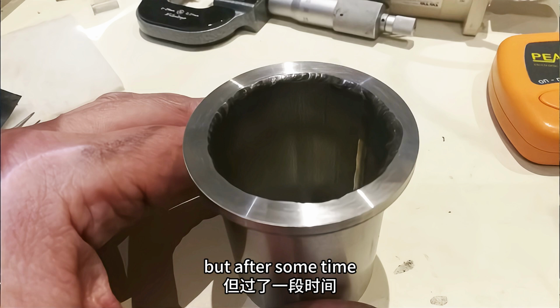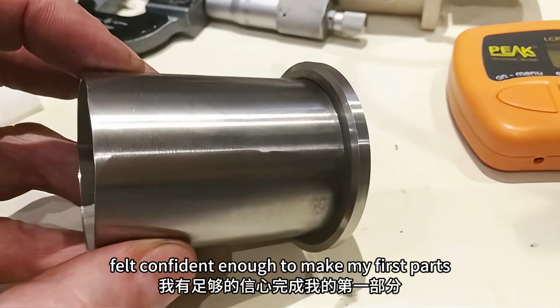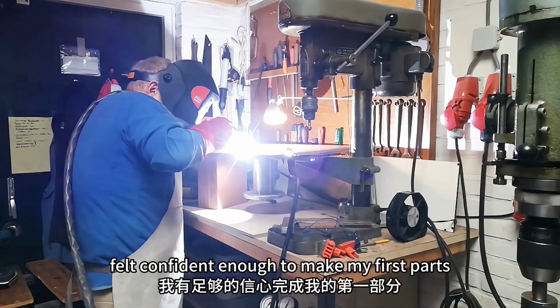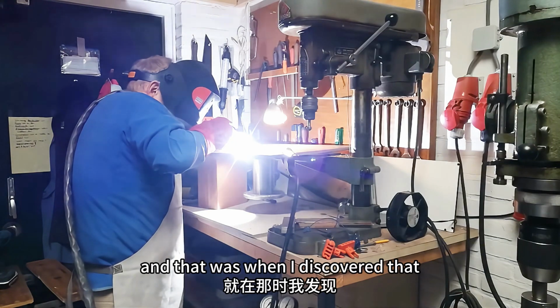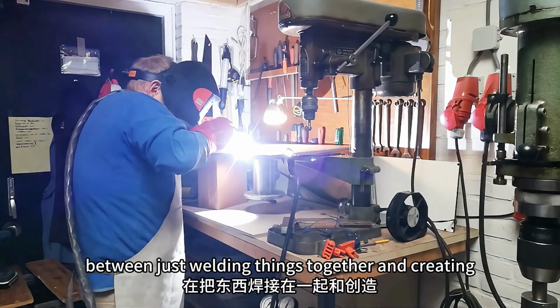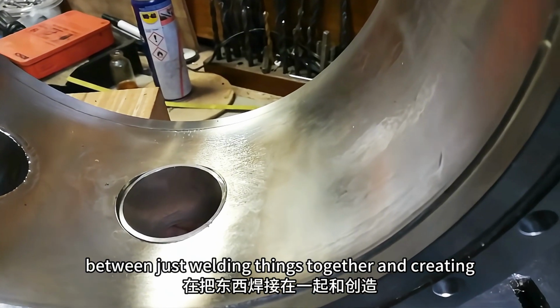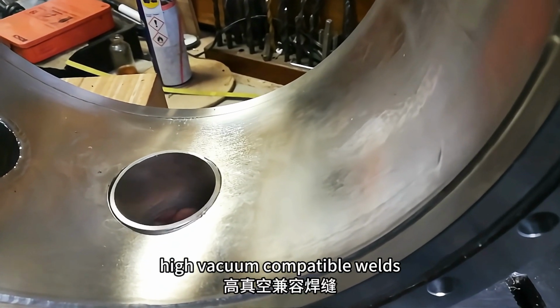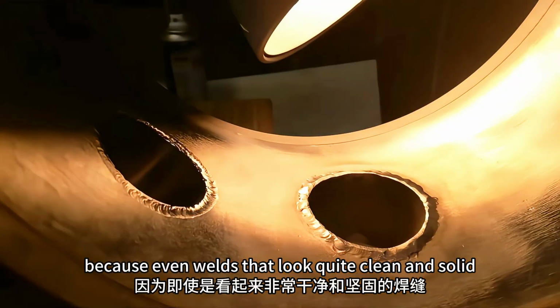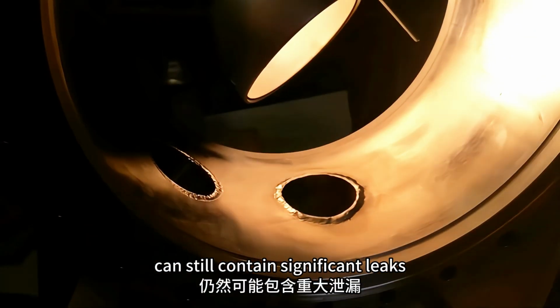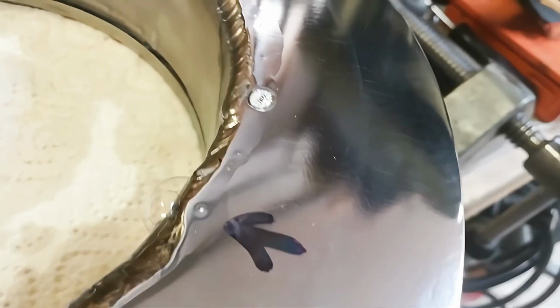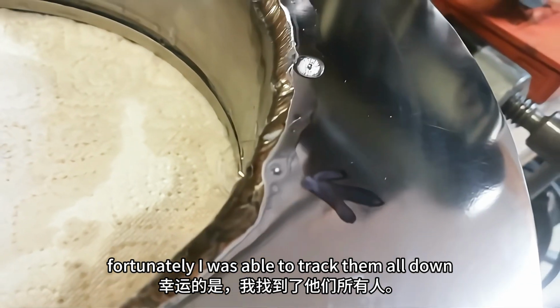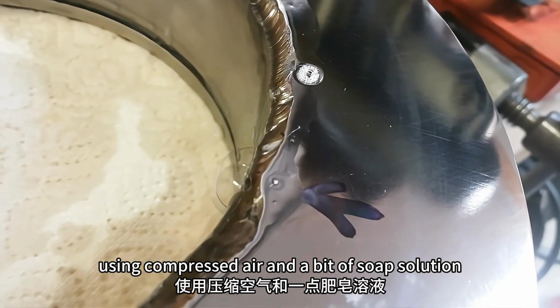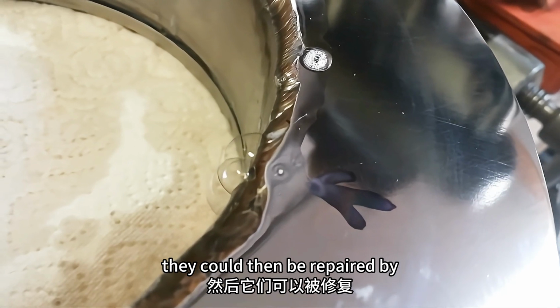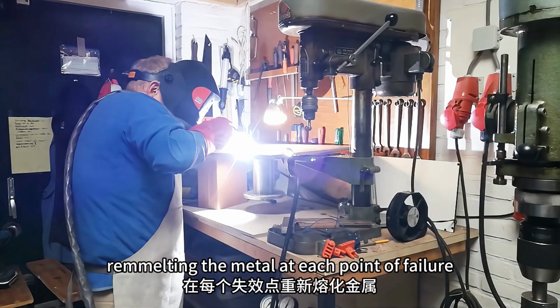But after some time I sort of got the hang of it and then felt confident enough to make my first parts. And that was when I discovered that there is a big difference between just welding things together and creating high vacuum compatible welds. Because even welds that look quite clean and solid can still contain significant leaks. Fortunately, I was able to track them all down using compressed air and a bit of soap solution. They could then be repaired by remelting the metal at each point of failure.